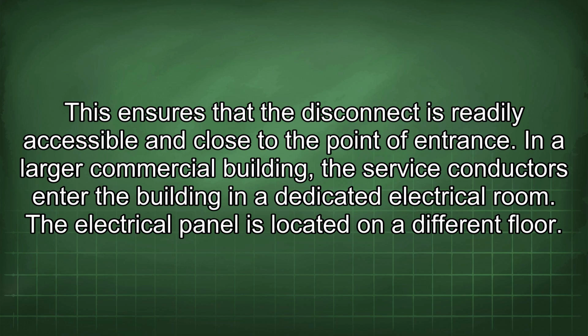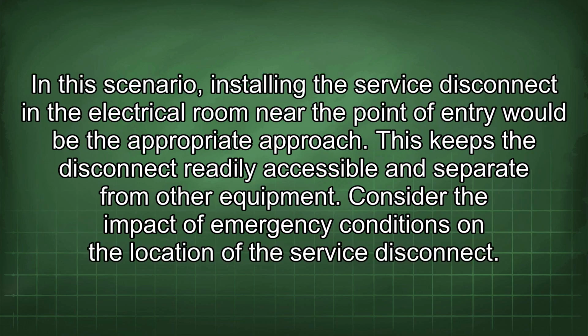In a larger commercial building, the service conductors enter the building in a dedicated electrical room. The electrical panel is located on a different floor. In this scenario, installing the service disconnect in the electrical room near the point of entry would be the appropriate approach. This keeps the disconnect readily accessible and separate from other equipment.